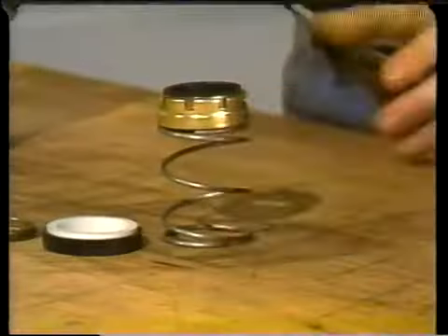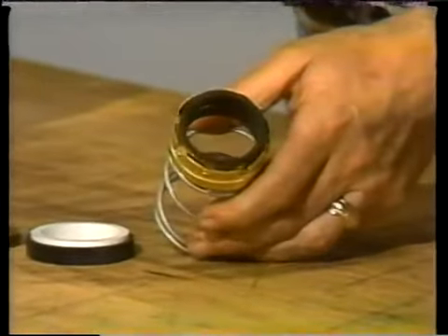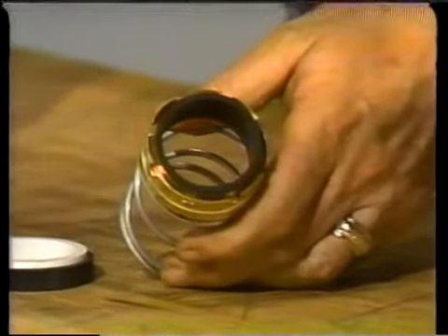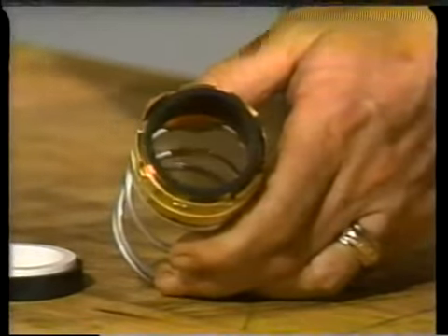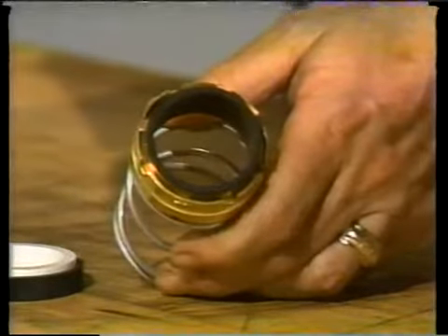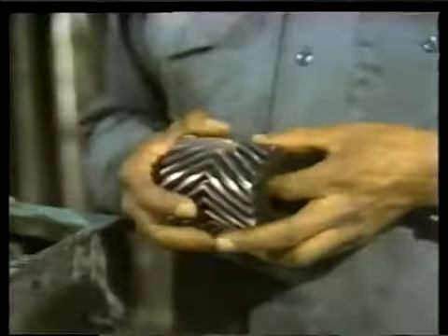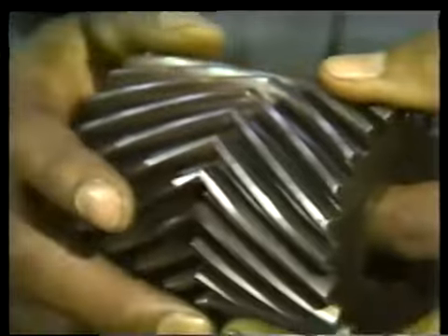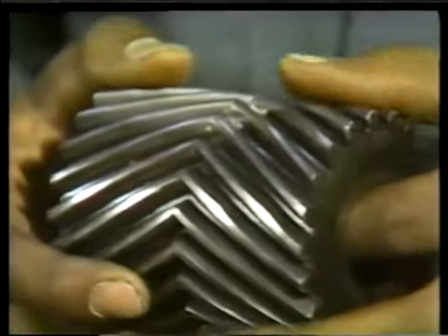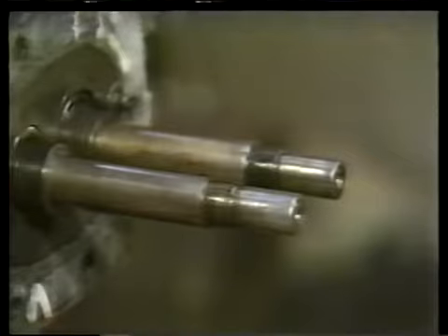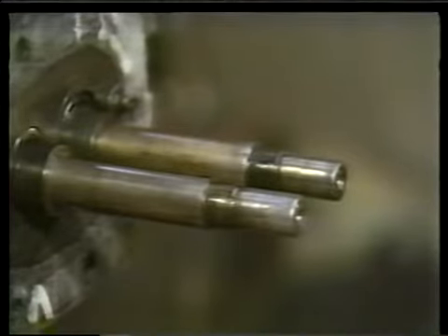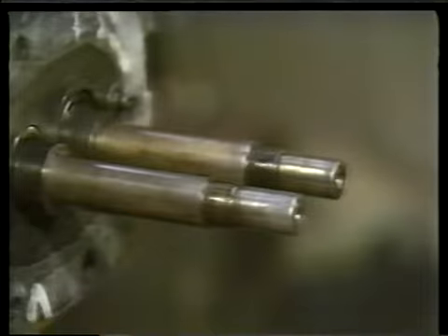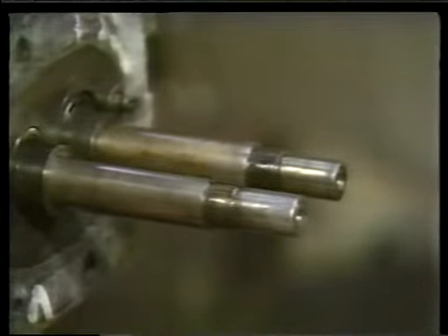Now, there are other types of parts that require careful handling because of their susceptibility to damage. On a mechanical seal, for instance, you want to avoid touching the carbon contact face. Even the grease from your finger can damage the face. Now, another sensitive area is any finely finished surface, such as the lands on a timing gear or a pump shaft. If bumped against a hard or abrasive surface, any nick or scratch can result in the part having to be refinished or even replaced.